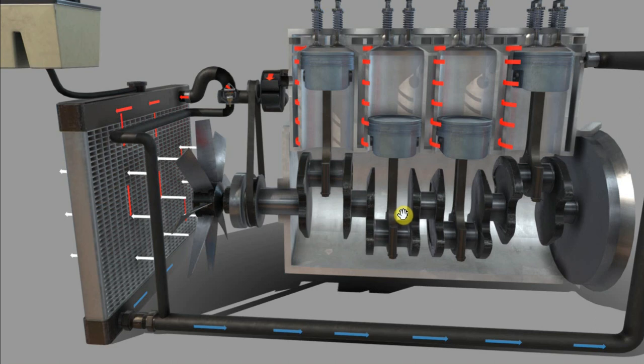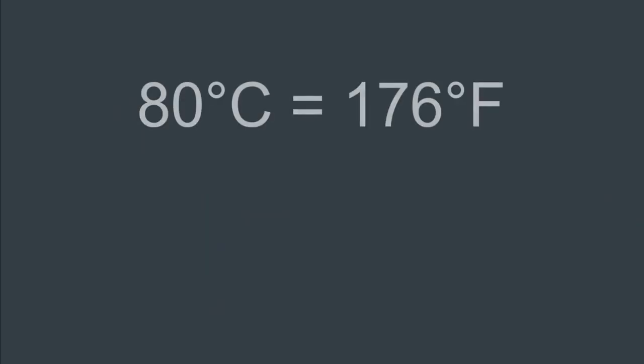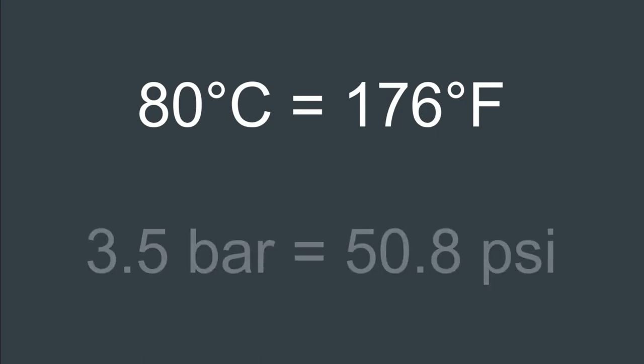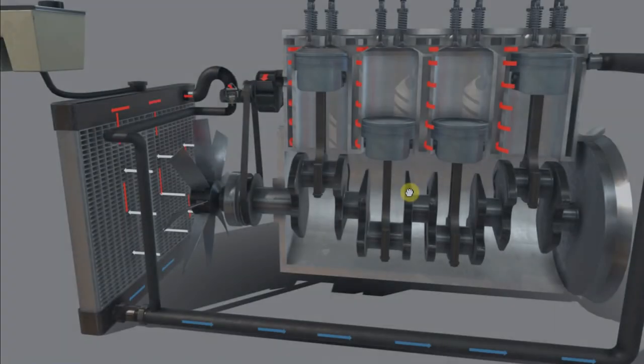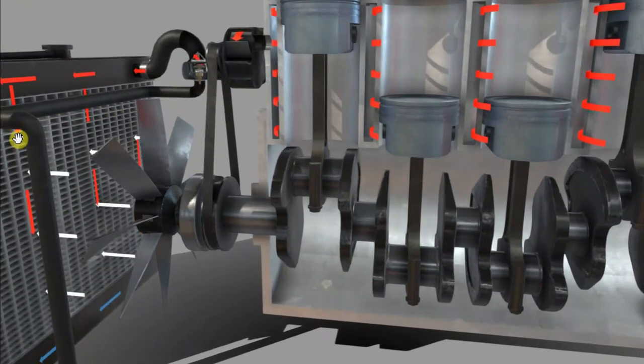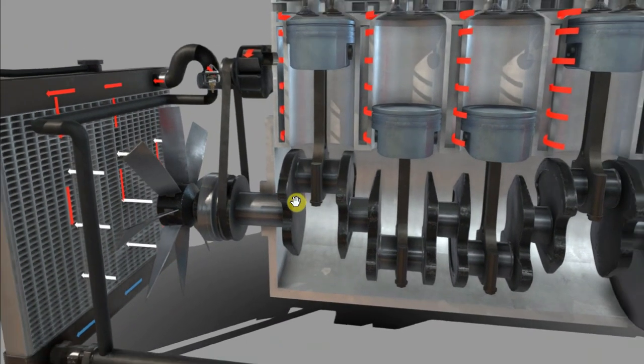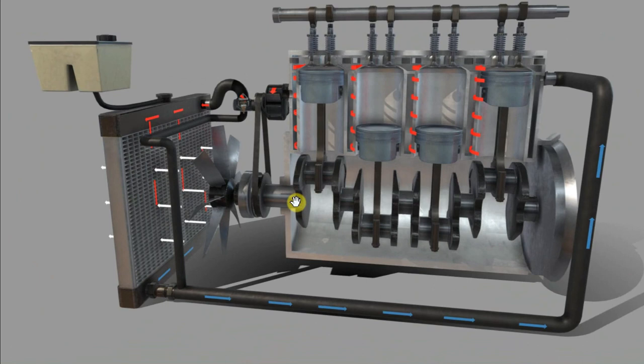A jacket water system will usually be around 80 degrees Celsius and approximately 3.5 bar of pressure. But that's essentially how the cooling water system works. When it's cold, we bypass the radiator, and when it's hot, we cool the cooling water down to a specific temperature in order that we can maintain the temperature in the engine at the optimum temperature.